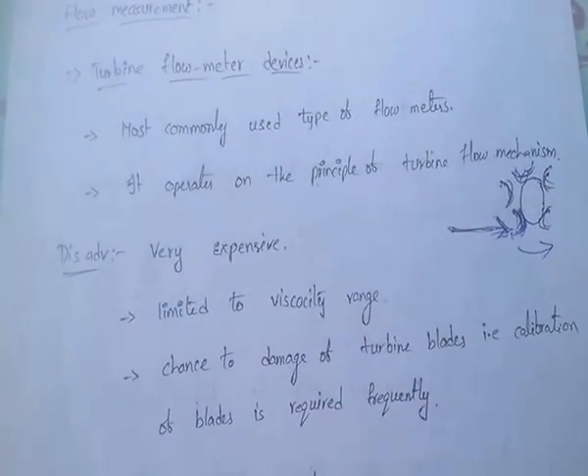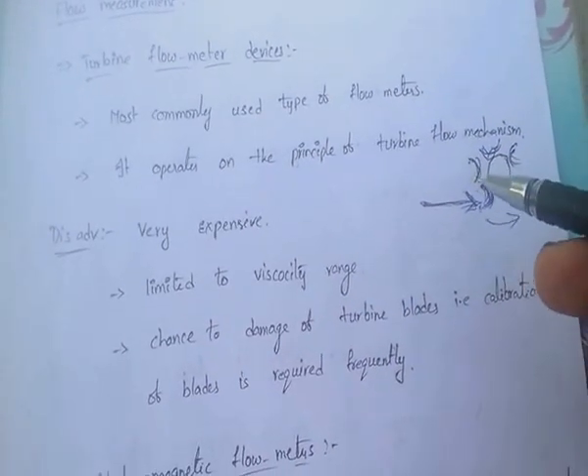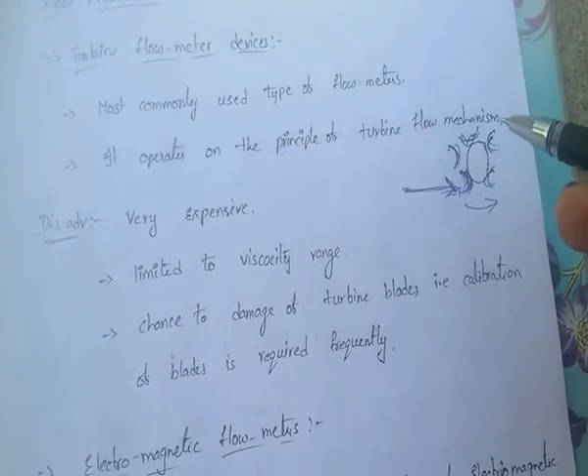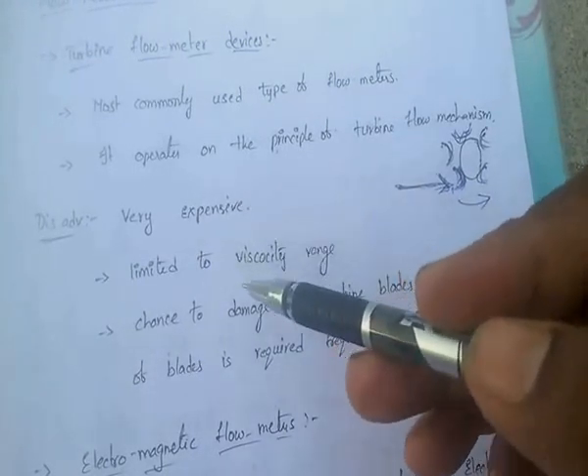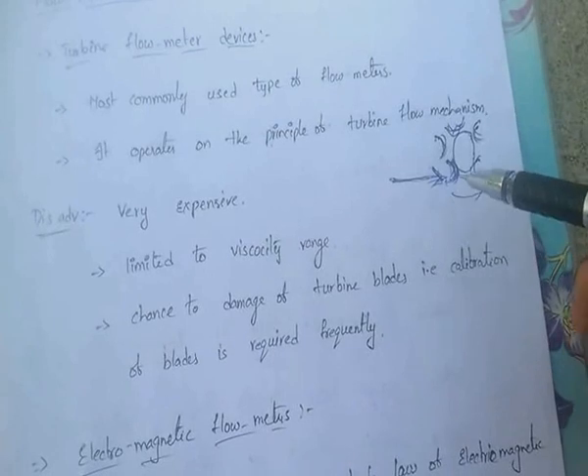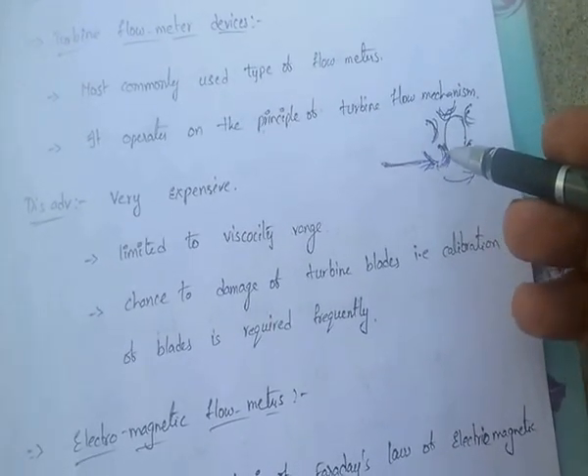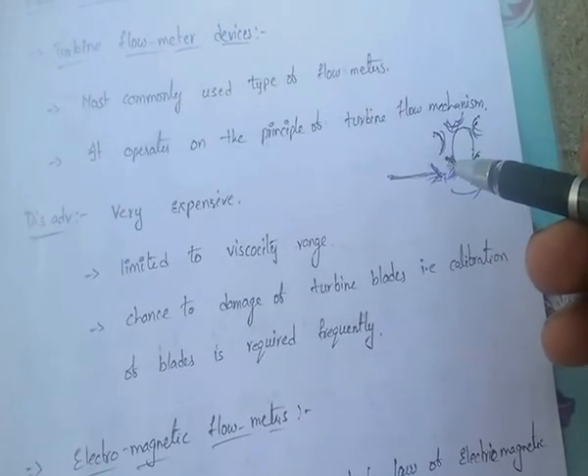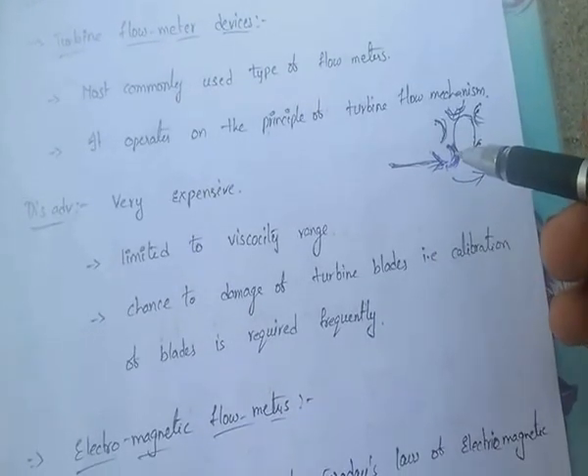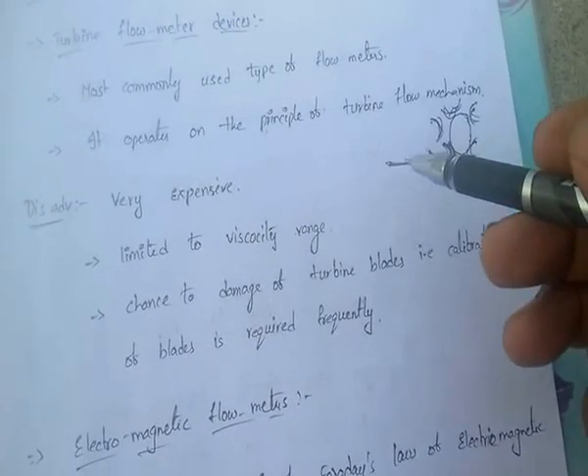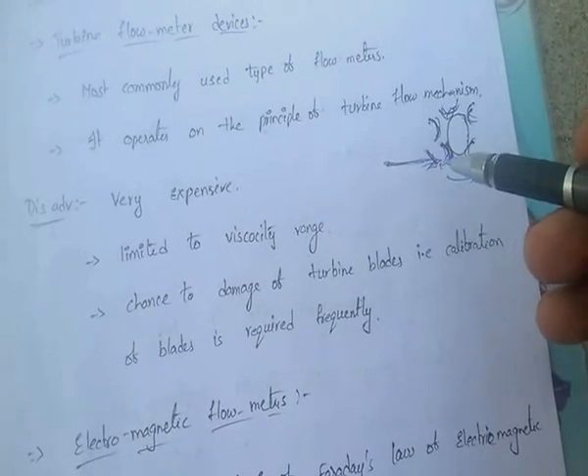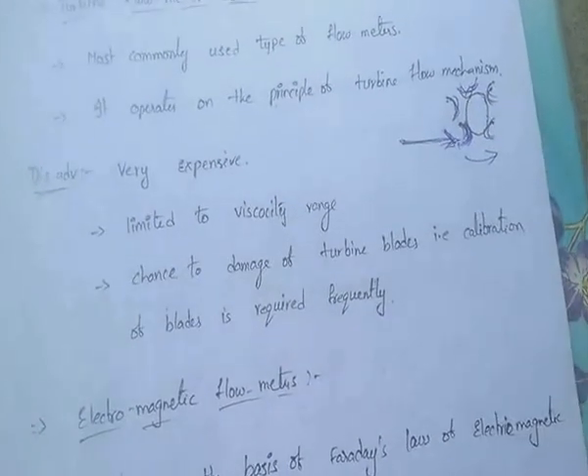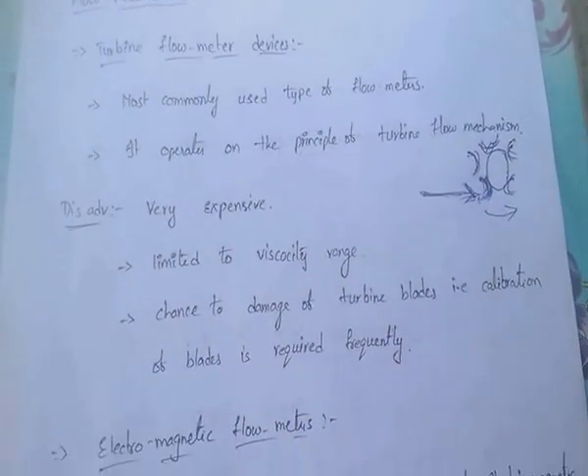The disadvantages of the turbine flow meter are: it is very expensive because of the construction involving turbine blades and the large amount of metal required. It is limited to a viscosity range. There is also a chance of damage to the turbine bucket blades when fluid strikes them. Frequent recalibration of the blades is required because their position may change due to fluid striking. These are the disadvantages of the turbine flow meter.